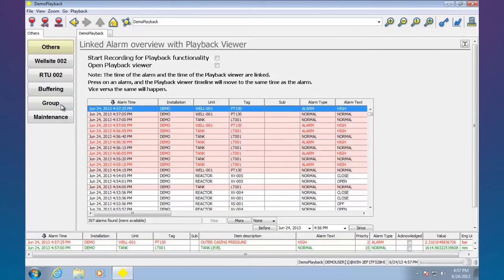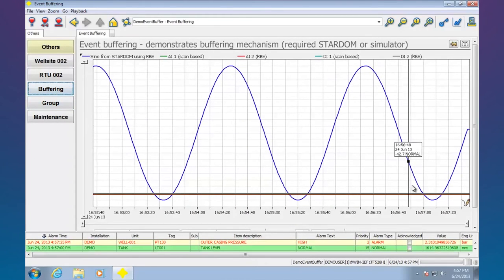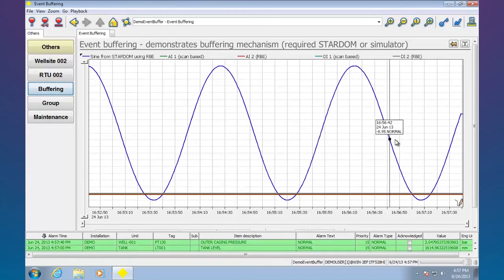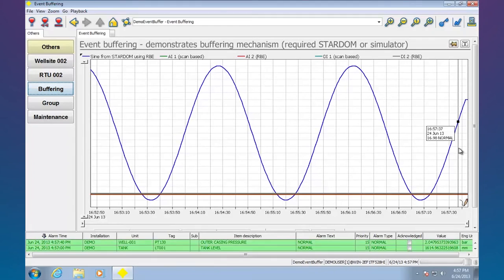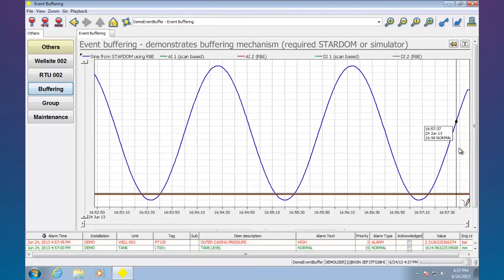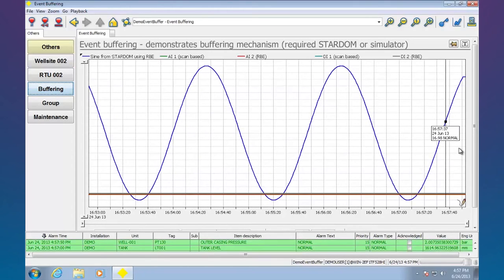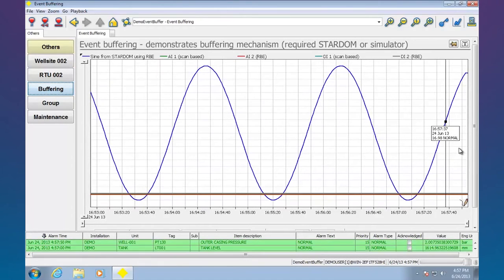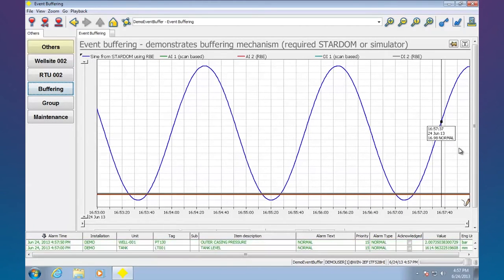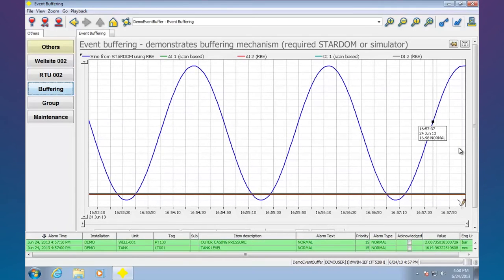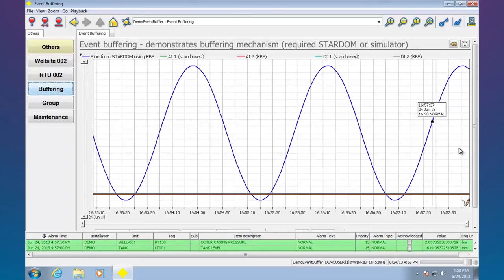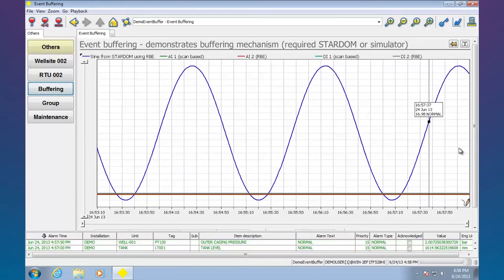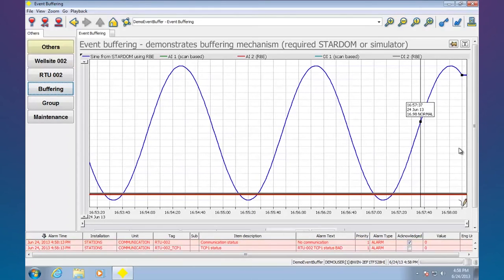Under Stardom here, let's take a look at something. This is a neat little thing. See how this sine wave is coming in? Well, this is coming off an actual Stardom unit that we have hooked up to the demo. I'm going to show you something relatively unique. When you combine the Stardom process automation controller or Stardom RTU with FastTools, we get something called event buffering. What this means is we won't lose any data if the PC goes down. We won't lose any data if the network connection goes down.